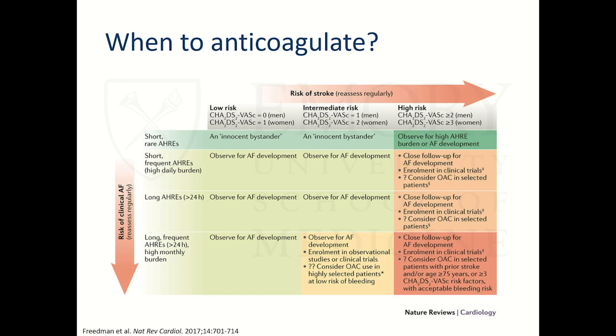So strictly speaking, what these devices are detecting is mode switch burden. There are a lot of mode switch causes that are not AFib, so when we get these reports, we actually try to adjudicate the electrograms. Is this sinus tach? Is it SVT? Is it something else? Is it noise on the device? We have to be careful. Not everything reported as mode switch burden is actually atrial arrhythmia. In the device trials, they report atrial high rate events, which are adjudicated as being AFib. But whether it's AFib or flutter, and whether the stroke risk is different, is unclear.